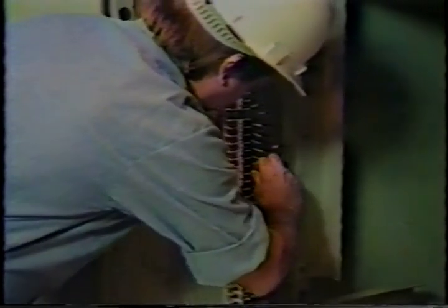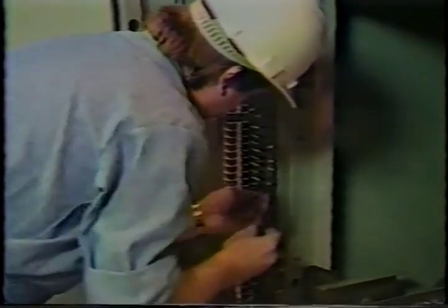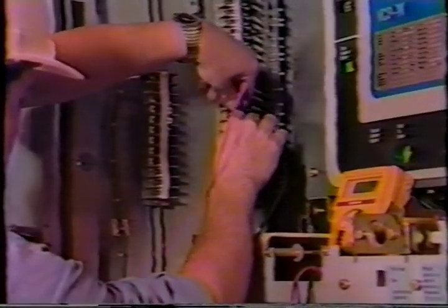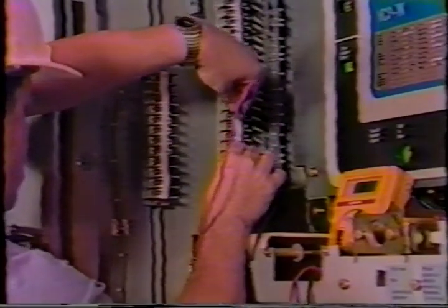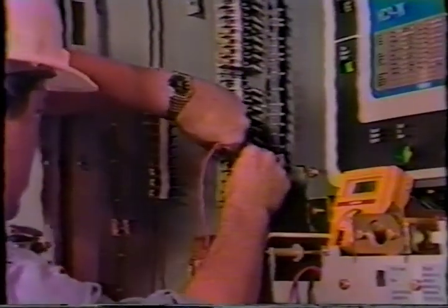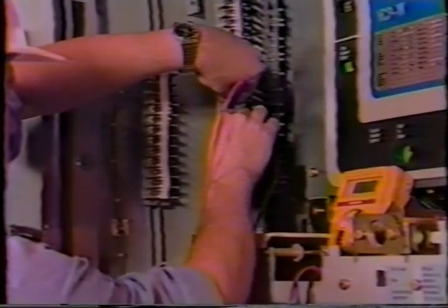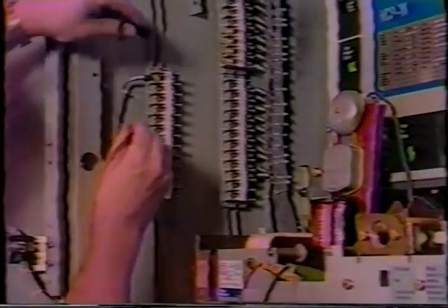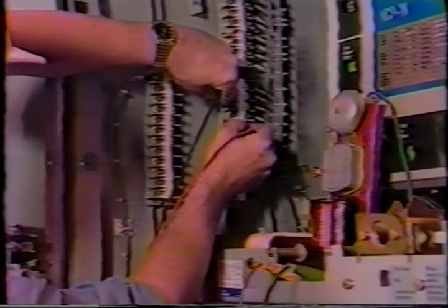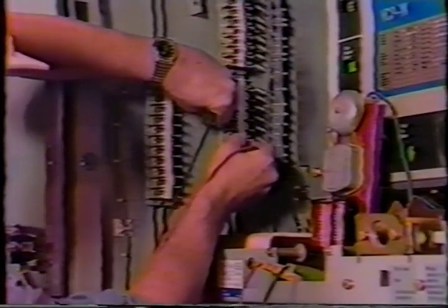Examine all wiring circuits to make sure they have not been damaged or loosened during shipment or installation. Make sure all the remote connections are correct before the equipment is operated. Light out connections between the switchgear and remote apparatus, such as instrument transformers, auxiliary switches, and remote control and interlock circuits. The testing equipment will depend on the size and type of installation. Use portable voltmeters. Rig up some simple device for ringing or lighting out circuits.